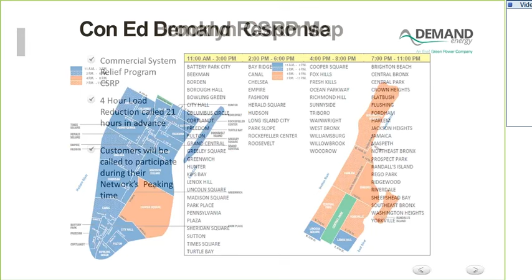There was no real significant interest by the DOB or even Con Ed, except to make sure we didn't have a safety factor where, if there was a power outage, this could feed back into the grid. They've since taken a lot more interest in what we were doing. The way I verified that they worked was to use the metering devices that handle the data for our demand response and cross-reference the output, the computer printout from the battery system, against that. We saw that when the system said it was injecting power, our meter slowed down. This was handled automatically, and sometimes I would call and say dump the power now, during a demand response event, and we'd see the 10 kW come off.